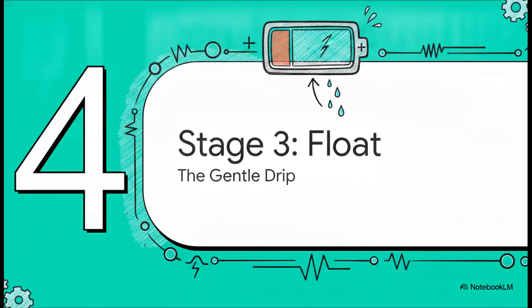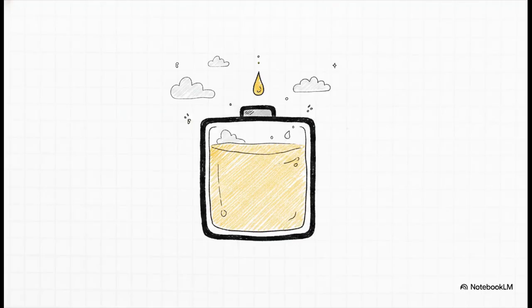Next up, section 4, stage 3, float maintenance, the gentle drip. Okay, assuming the controller perfectly nailed that absorption balance, your battery is now 100% full. Now, the goal of float is active maintenance. We want to keep the battery at exactly 100% fullness, but we absolutely cannot subject it to the high voltages we use during absorption. Prolonged high voltage exposure will literally cook a battery. So this stage exists strictly to compensate for natural passive self-discharge.